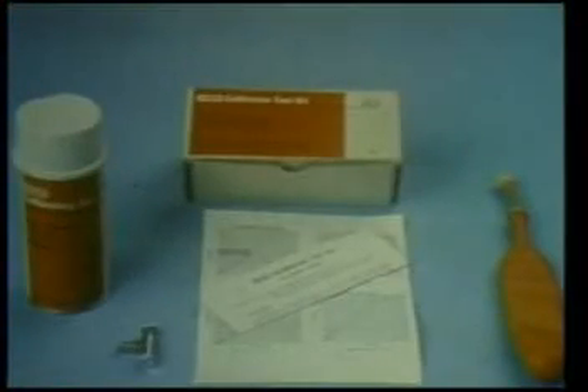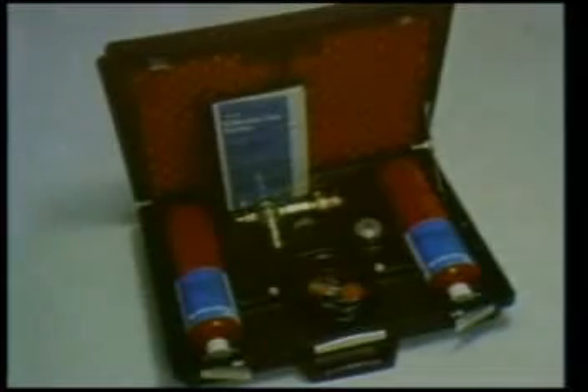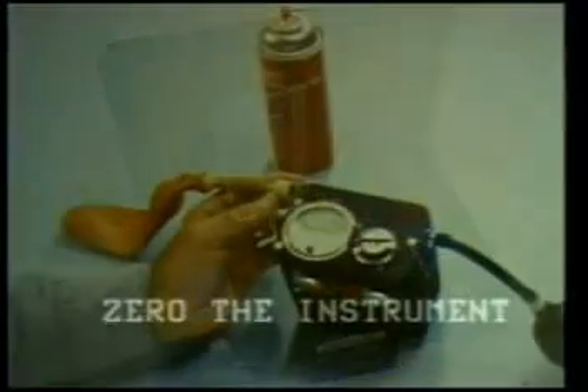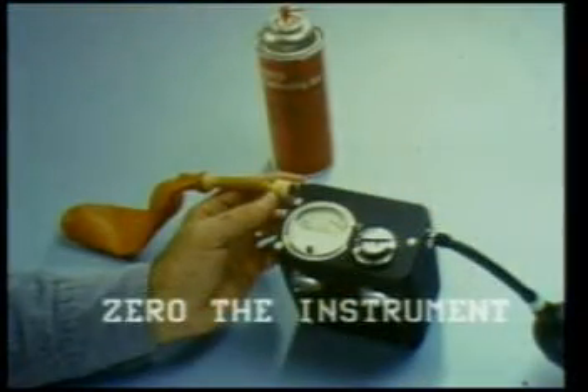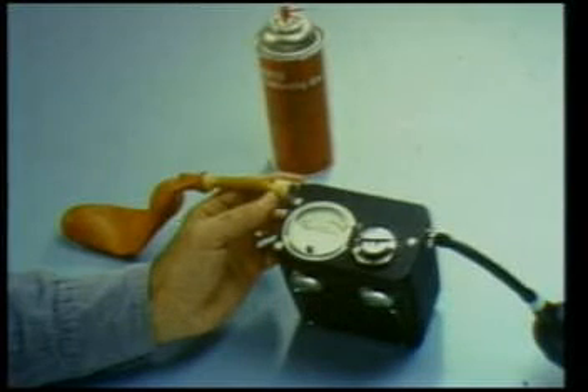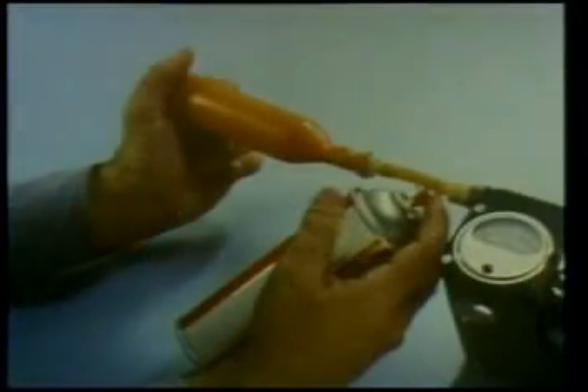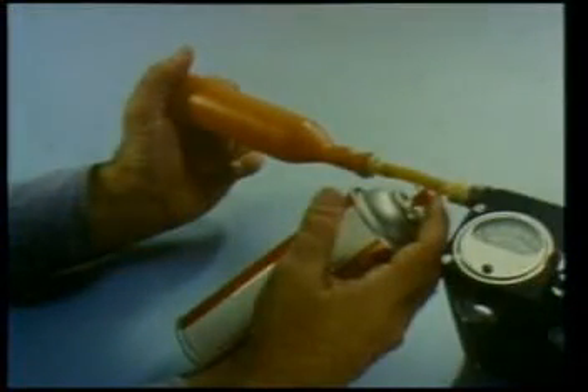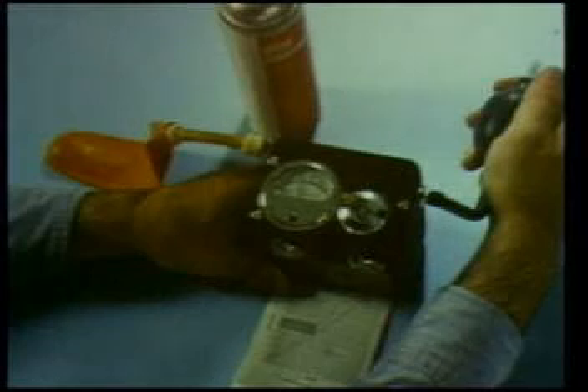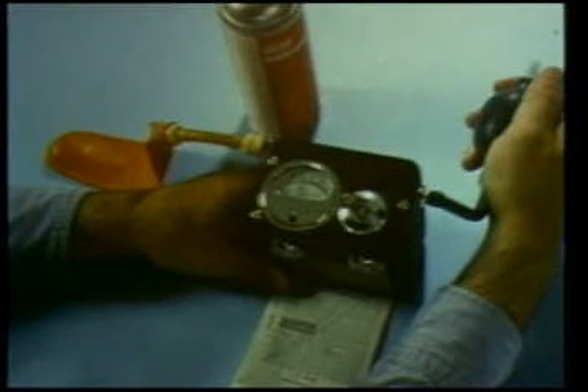The calibration may be checked in the field with a portable test kit or check kit containing a known concentration of methane in air. The first step in the calibration check process is to zero the instrument. If you're using the calibration test kit, connect the bladder assembly to the inlet fitting of the instrument. Insert the needle of the aerosol can of calibrating gas into the tubing, not the bladder, and press the button to inflate the bladder. Squeeze the aspirator bulb to draw the calibrating gas from the bladder into the instrument. Compare the upscale meter reading with the response curve for the Explosimeter Model 2A furnished with the test kit.